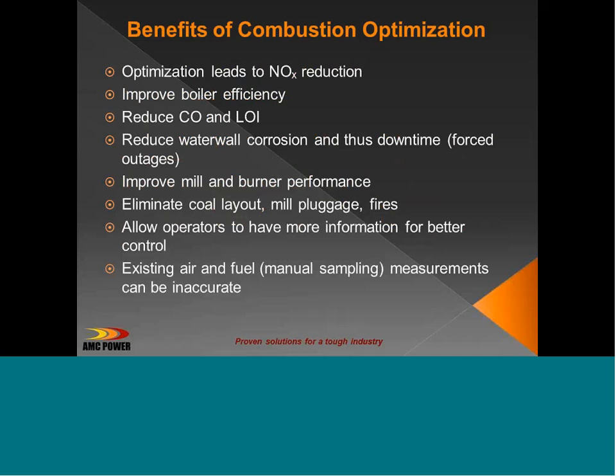The reasons people are getting involved in combustion optimization are various. A lot of utilities use this for different reasons. Some people use some of the products, like overfire air measurement, just as a NOx reduction tool. Some people are using complete air and fuel optimization systems to reduce CO, to reduce NOx, to reduce unburned carbon. Lately, there's been a lot of fuel flexibility issues, people wanting to burn coals that don't burn well in their furnaces, so they're using equipment like ours to help them burn better without CO and slagging problems. Water wall corrosion and downtime is another issue that comes into being with that as well.